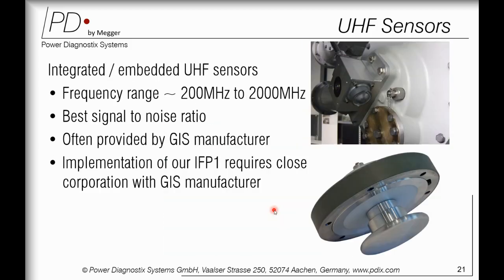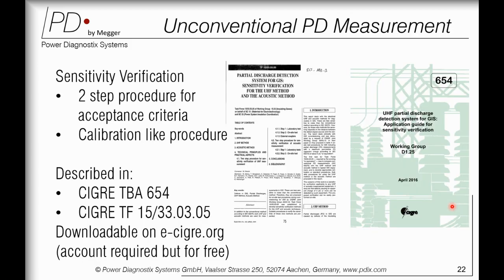The inbuilt UHF sensors typically used in the GIS have a frequency range from 200 megahertz to 2000 megahertz. They have the best signal to noise ratio and are often provided by the GIS manufacturer. Implementation requires close cooperation with the GIS manufacturer, of course, and these inbuilt UHF sensors are typically given by the OEM itself according to their design. So this was the overall basics: what is PD, what are the different measurement techniques, and what are the solutions when you have inbuilt UHF sensors.